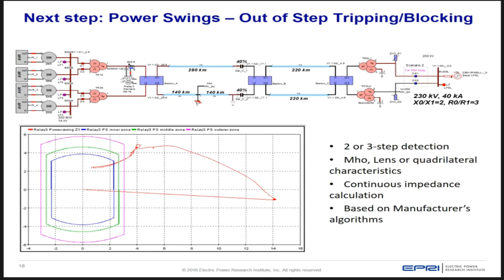Yeah, one thing, and I'll talk about it in my presentation, we found higher order harmonics are a real challenge for protection, because most of the time relays, CVTs, CTs, and all that have poor frequency response above about 600 hertz. Okay. Yeah, that's a good thing. We can consider it in that. The CT models that are developed include magnetization, right? So you can also do that. So yeah, the models have the capability.